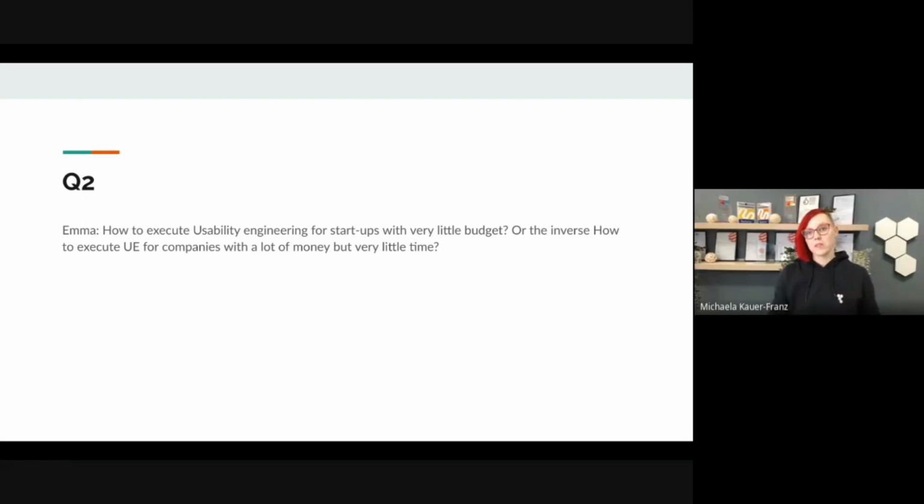Yeah, so seen from a regulatory side of things, you need to have the documentation in place. Just as simple as it is, which basically is going to check for the required contents. It's, I don't know, 10 points. Please don't nail me on the number. And you have to have a file which tells you, I have considered those 10 points, and you have some kind of documentation. And depending on the criticality of your device, this can be very short. So I've seen successful usability engineering files that just contain 1.5 pages. So really, if you have a low-risk device, or however you call it, a no-risk device, get the documentation ready.